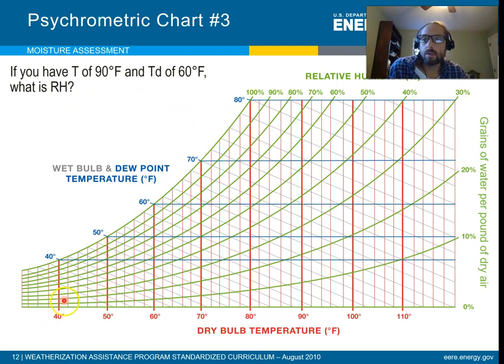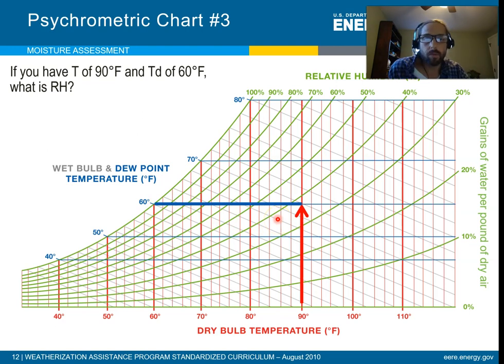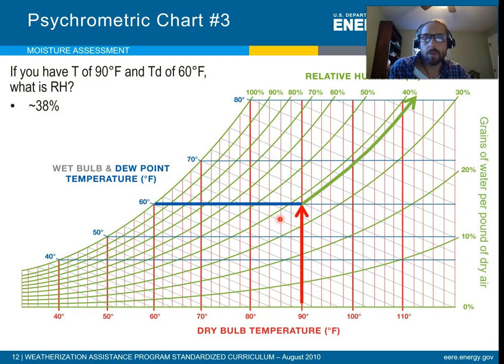Let's do another example. We have a dry bulb temperature of 90 and a dew point temperature of 60. What's the relative humidity? We find a dew point of 60 — remember, it's horizontal from the dew point. We have 90 degrees on the bottom. The relative humidity — you have to do a little interpolation — and we get about 38%.